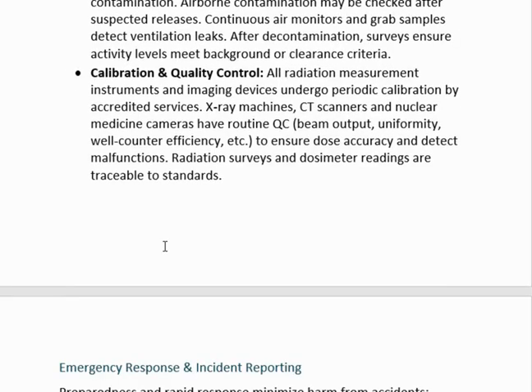Calibration and quality control. All radiation measurement instruments and imaging devices undergo periodic calibration by accredited services. X-ray machines, CT scanners, and nuclear medicine cameras have routine QC, beam output, uniformity, well counter efficiency, etc. to ensure dose accuracy and detect malfunctions. Radiation surveys and dosimeter readings are traceable to standards.